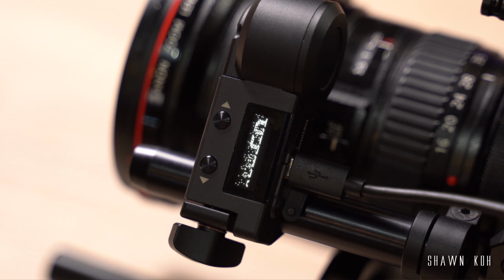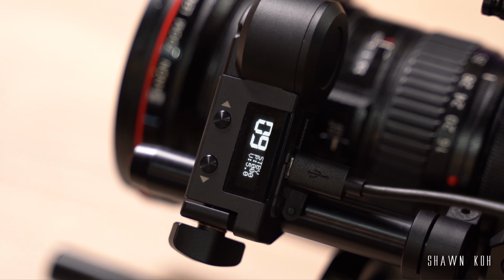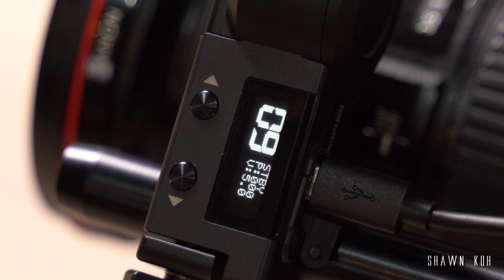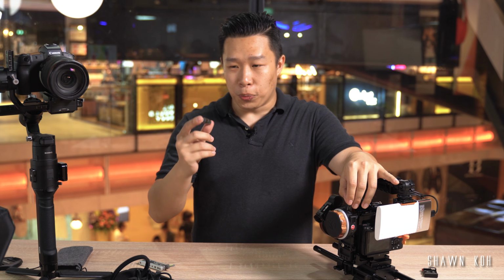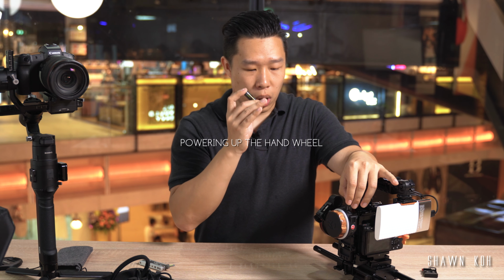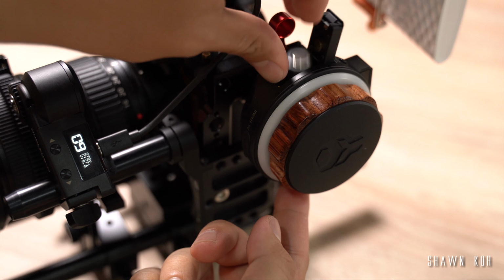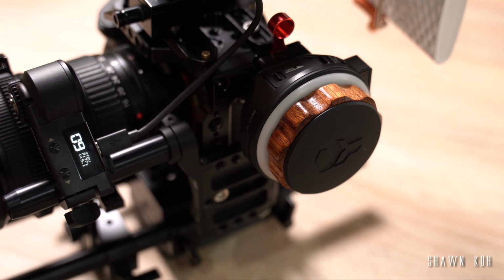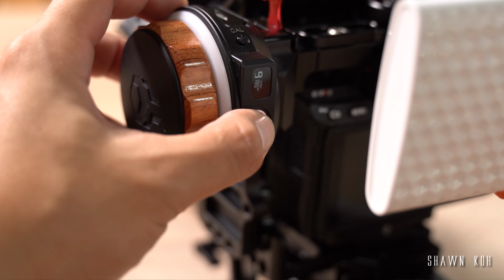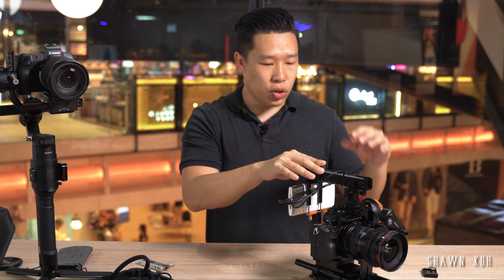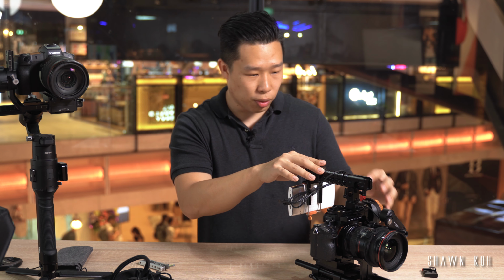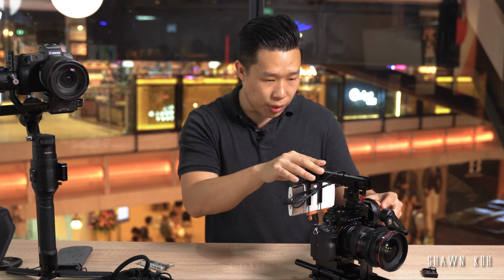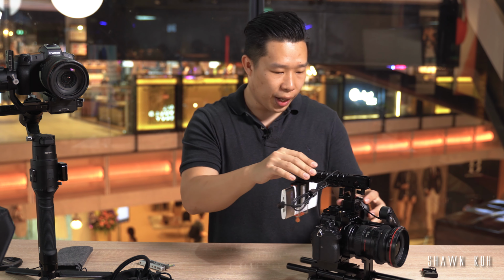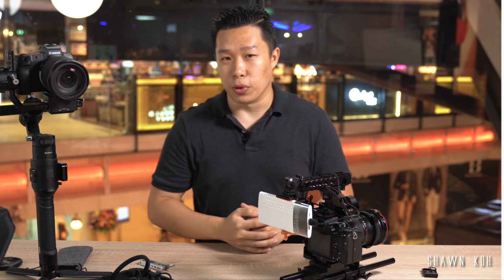Alright, so with that all turned on, you can see which channel you're on, the standby mode, as well as a reading of how much your focus wheel is turning. Alright, so we also have to put in the rechargeable battery to power up the focus hand wheel. It goes in on the negative side down. Alright, so with that all done, you can press and hold the red button and that will power up the whole system. Right out of the box, it should come already paired. Mine is on channel 9 and I just have to turn the wheel a bit to see that it is working and I can go ahead and start my calibration process.